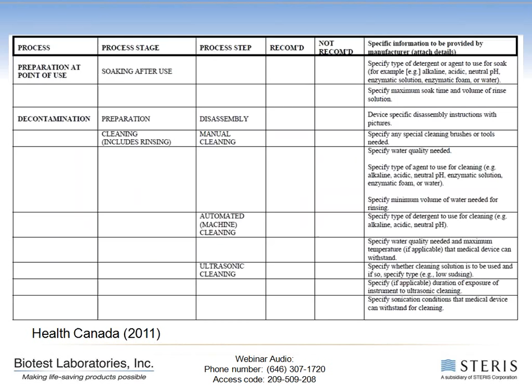As Jerry mentioned previously, the FDA have recently become concerned about instructions for use and have published draft guidance for processing, reprocessing reusable medical devices in May of 2011. This guidance highlights 7 criteria for medical device reprocessing. These include correct and detailed labeling that reflects the intended use of the device, a change in perspective on the details for cleaning and how that is validated, requirements for statements of disinfection and/or sterilization based on the Spaulding classification, clear but also practically and technically feasible instructions, the use of equipment and accessories that are legally marketed in the intended country. This will include defined sterilizers, washer disinfectors, cleaning chemistries, and high-level disinfectants, among others.